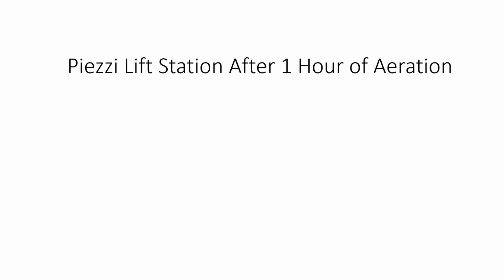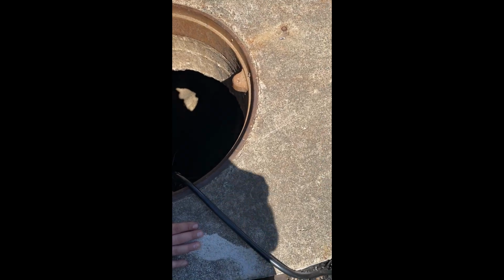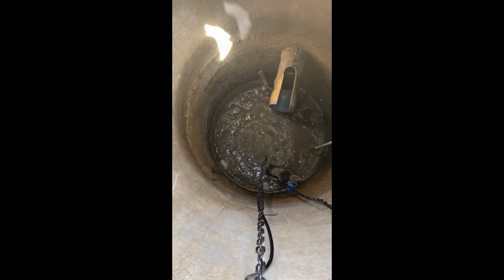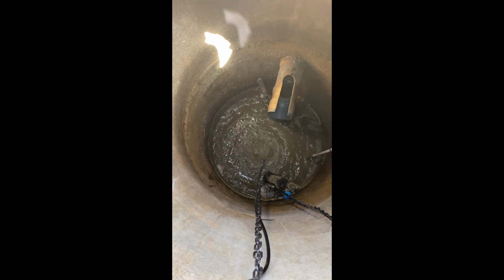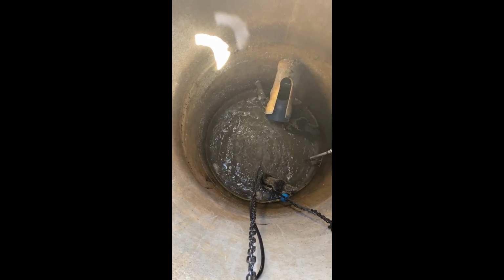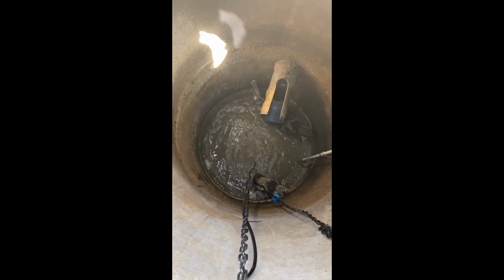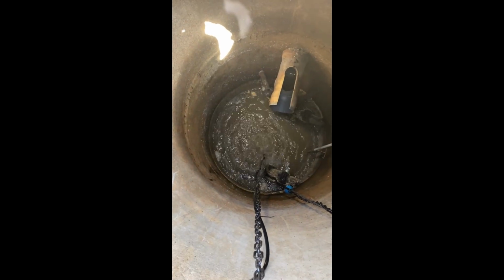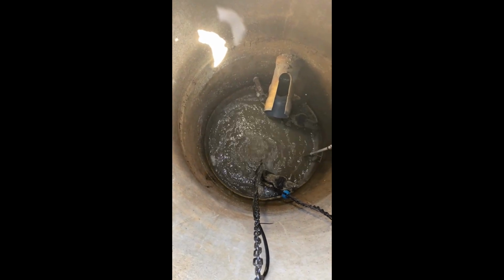So this is going to be Piezzi Lift Station after 1 hour of aeration. This is Piezzi Lift Station, 1 hour into blowing air bubbles. There was a little bit of a cap on. They had just barely sucked this down with a cleaning truck, so it didn't have a thick cap. But there was a little bit of a cap here. And as you can see, pretty much nothing, nice and clean.